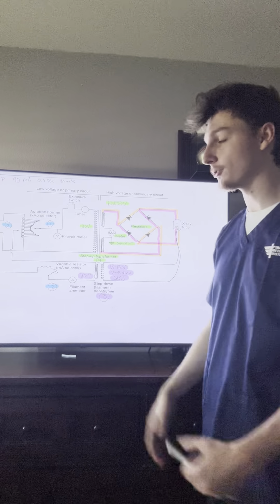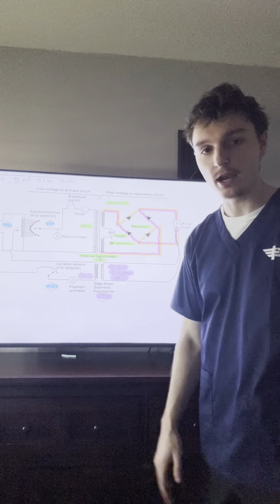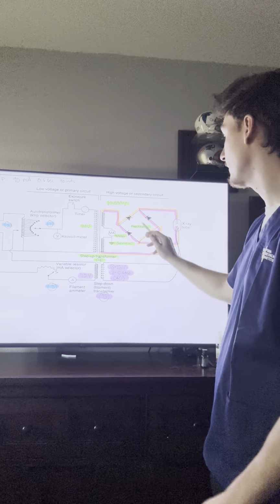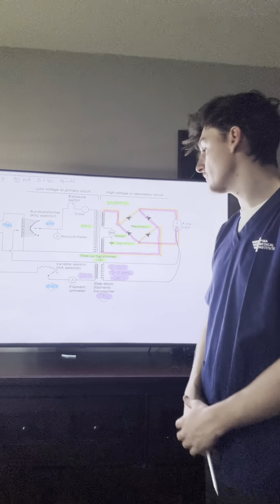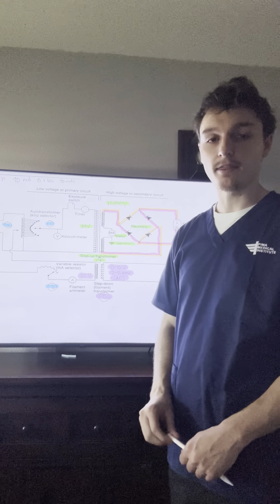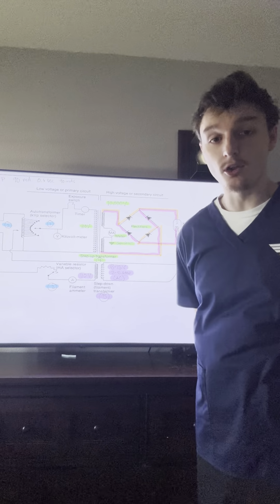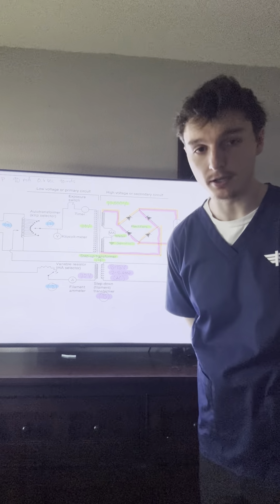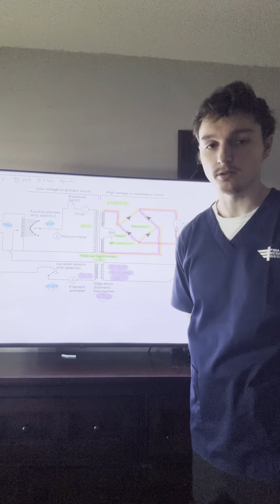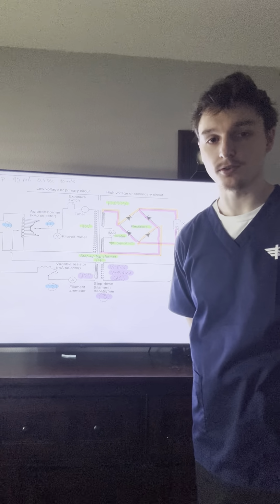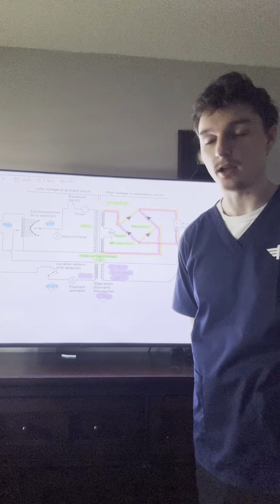Now that we've got our 10,000 volts into our capacitor and falling load generator, with our MA meter and exposure time switch working, we can talk about the rectifiers. The rectifiers change that 10,000 volts of alternating current into pulsating direct current, so it's 10,000 AC converted to 10,000 pulsating DC.